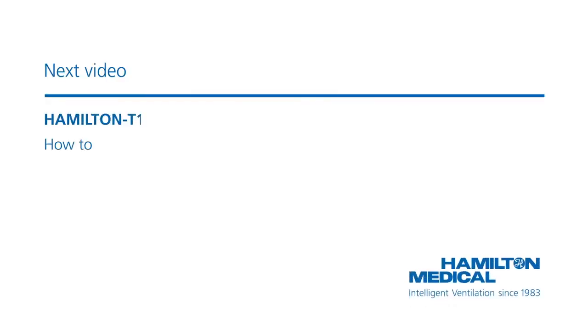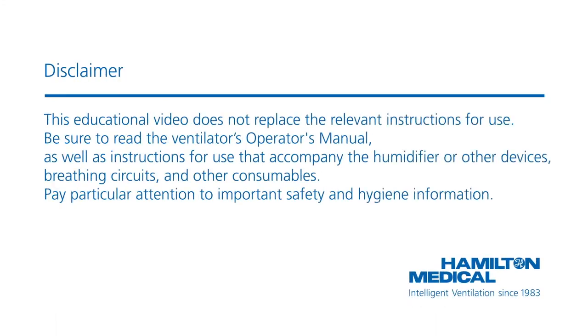It's best to keep the ventilator connected to its primary power source to maintain the battery charge and extend the battery's life. This educational video does not replace the relevant instructions for use. Be sure to read the ventilator's operator's manual, as well as instructions for use that accompany the humidifier or other devices, breathing circuits, and other consumables. Pay particular attention to important safety and hygiene information.